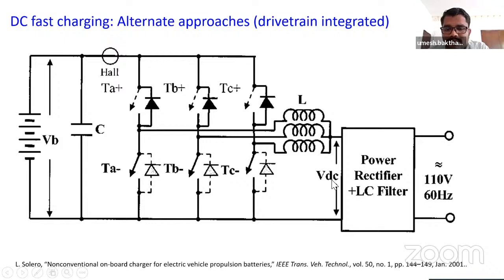So here there is a DC voltage, so the motor will not rotate. Basically you are applying DC currents into the EV motor. The motor is an AC motor - induction or PMSM - but you are pumping DC current instead of AC. So the motor will not rotate for DC currents. It will only generate some harmonics, and if you maintain a lesser current than the AC currents, the motor will not even heat up. So there is no harm to the motor when using it this way in a charging station.